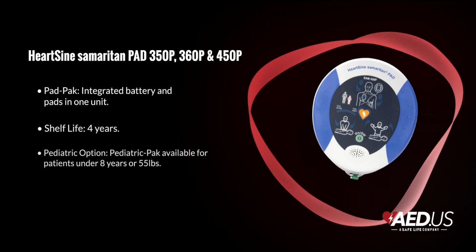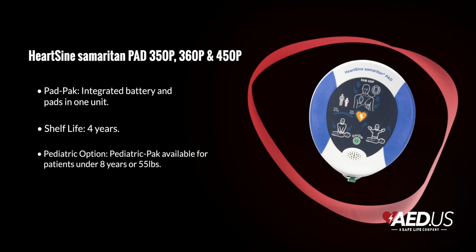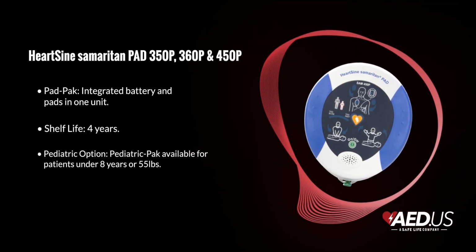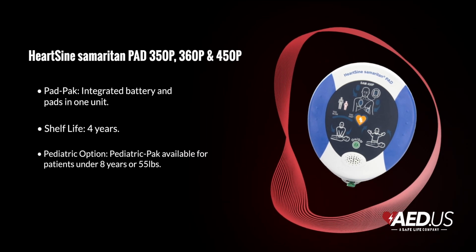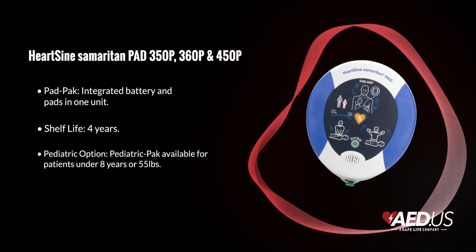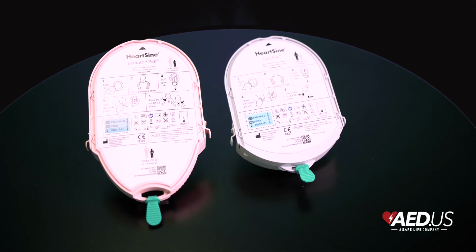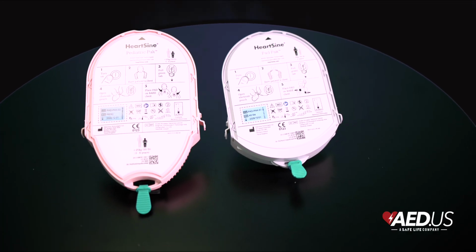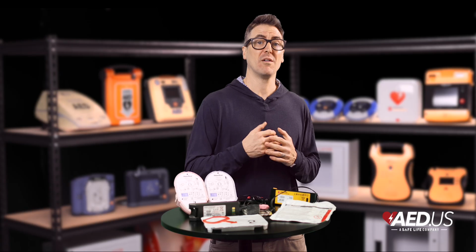These AEDs use the innovative Pad-Pak system, an all-in-one design that combines the battery and pad into one single cartridge. The Pad-Pak simplifies maintenance with just one expiration date to track and one component to replace.